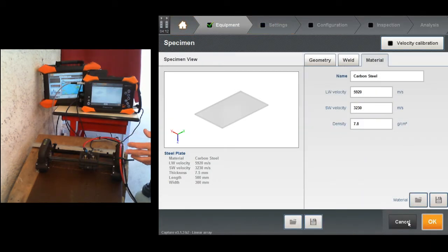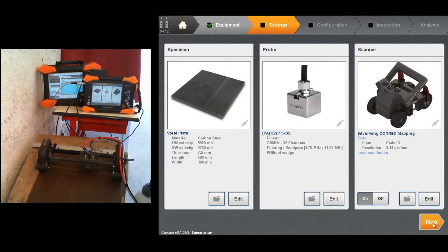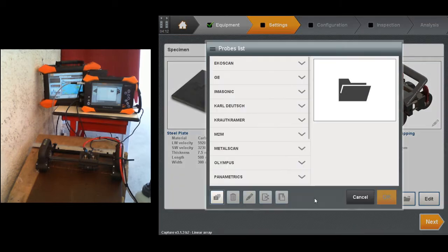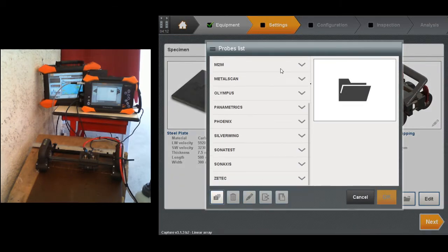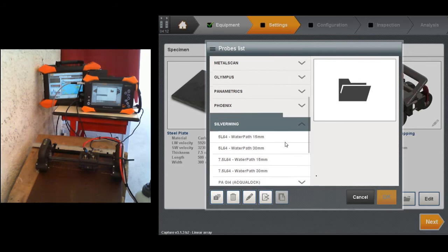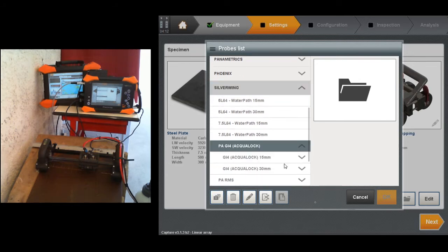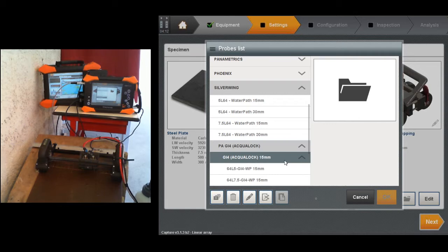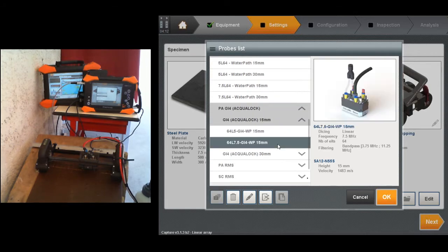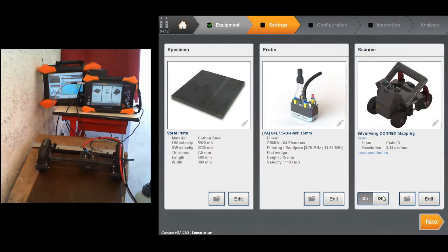In this case, I have no cal block here, quite accurate, and then I cannot really calibrate on that for sure. So I can keep these parameters, which are very good at first. So my specimen is done, and then I can go to the next step and select the probe. So here I need to select from Silverwing the Aqualock with 7.5 megahertz. Water column is about 15 millimeter, but I will measure it.